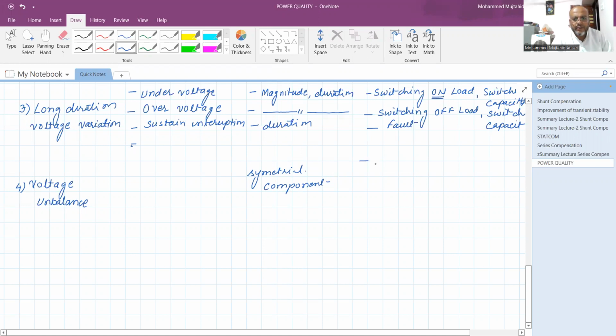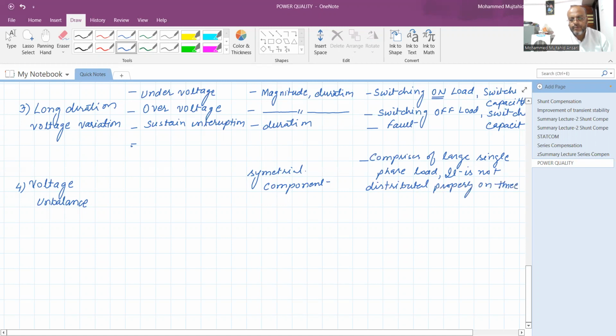And what is the reason? Suppose the premises or the load comprises large single phase loads, and it is not distributed properly on three phase. So it may be the cause of unbalanced voltage. It may be a large number of single phase loads.